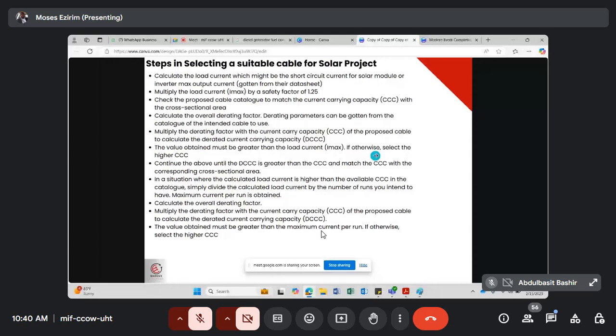The capacity must be greater than this cable's value, and what value did we obtain? 22, right - must be greater than now. Let's assume the derating factor, let's assume we are passing the cable under the ground, that it is a ground mount, and we are considering the burial depth, the soil resistivity, the duct derating factor and the rest. So after multiplying everything together, you get 0.5. Now when you multiply 0.5 times 30, what will you get?